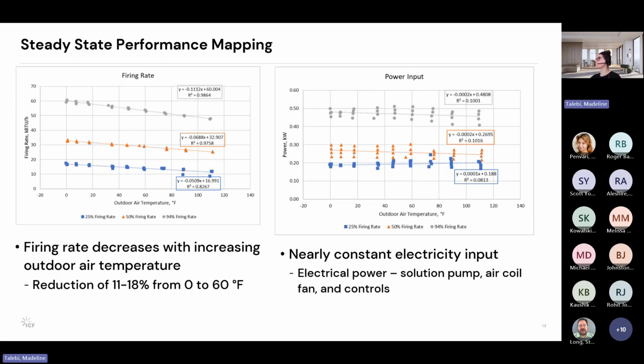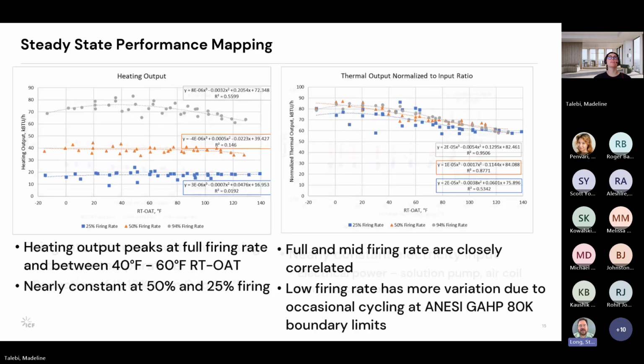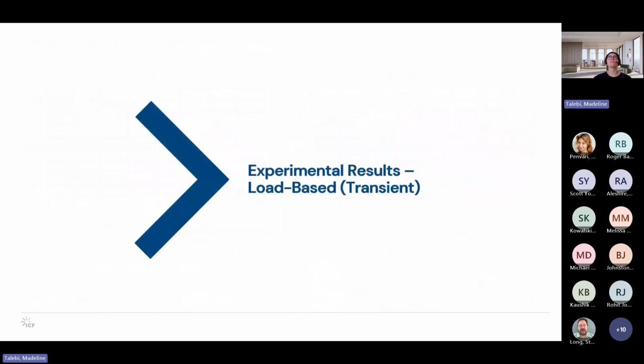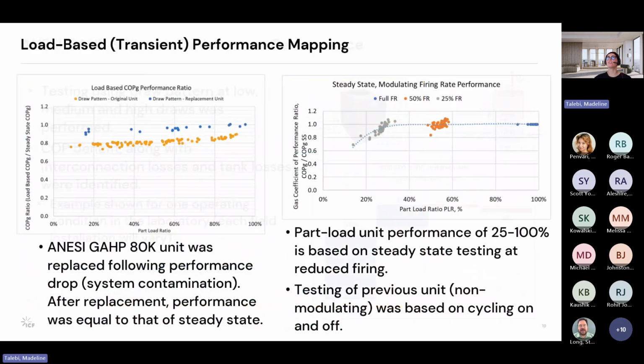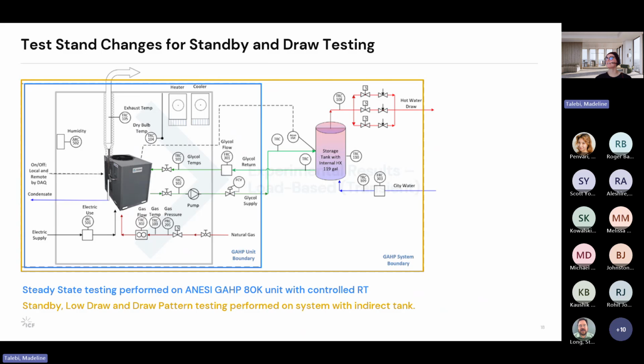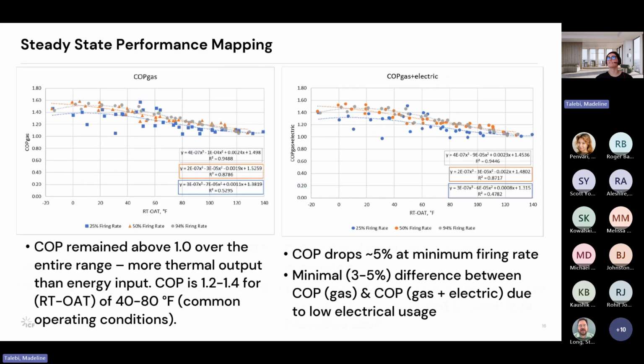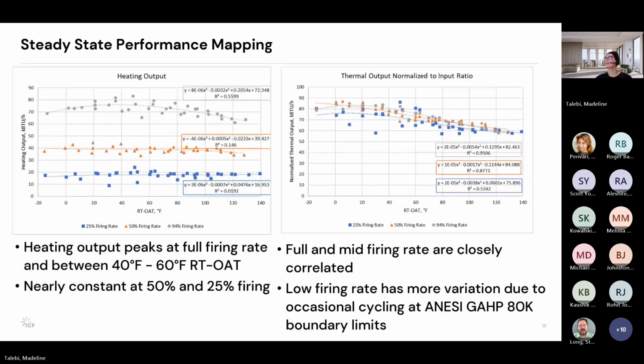Any idea what causes the variation in capacity and COP at similar conditions but different tests? Sorry, are you referring to the part load, different tests in that regard? Or are you talking about the steady state testing? Because if it's the steady state testing, it's just attributed to the difference in the firing rate, which they purposely adjusted for.